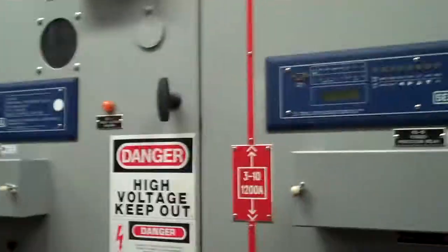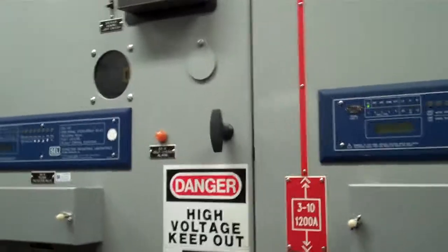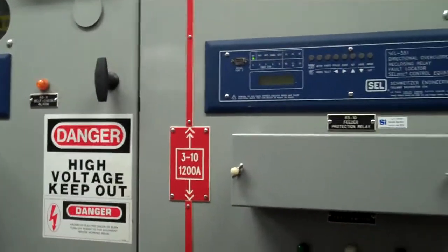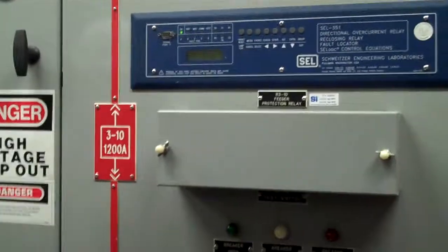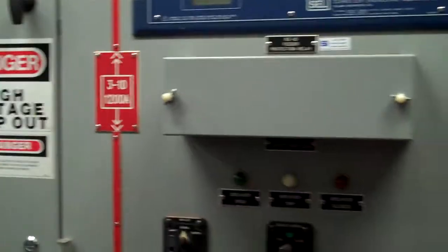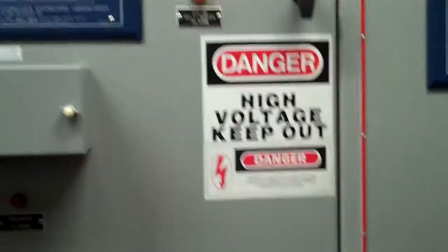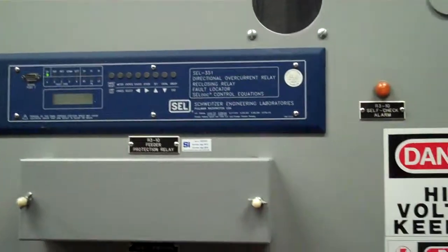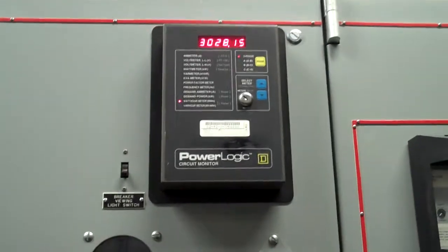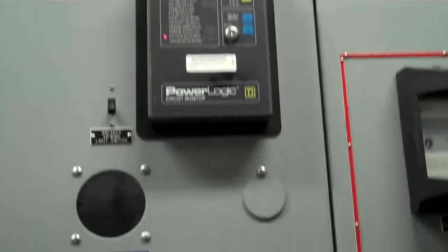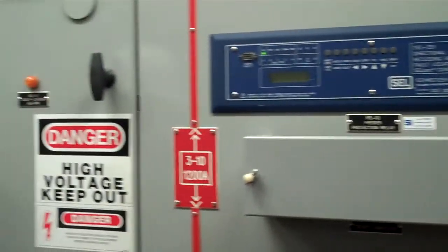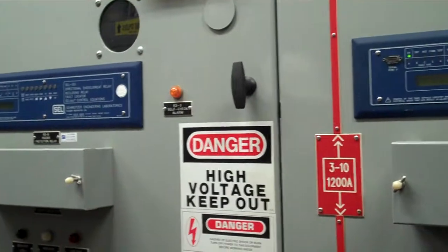This bus just feeds the plant. The bus above goes out and feeds all the campus buildings. They're not tied together. Obviously the fault capacity, generation capacity of the generator is pretty large. So one of the biggest reasons I mentioned earlier is to reduce that fault capability, which is fundamental. For years they used to run with everything tied together. So we decided to split it instead of putting reactors throughout the system.